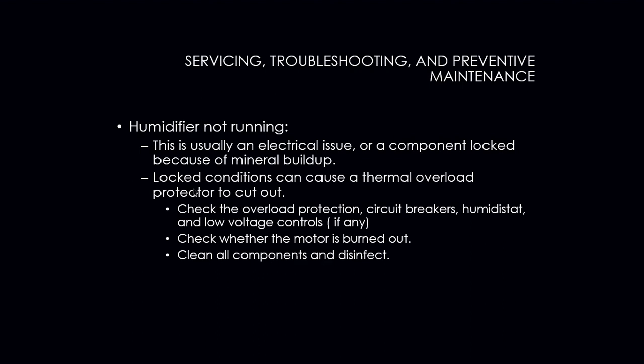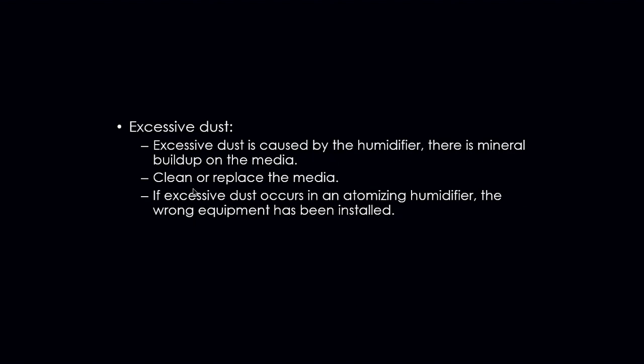Okay, you want to check the overload protection on a humidifier. You want to make sure the circuit breakers, your humidistats, any sort of voltage issues, low voltage controls, all that stuff is on and functioning. You need to check whether or not the motor is burned out on a humidifier. We need to make sure that all of the components are clean and disinfected. Okay, so remember, we are doing maintenance on services. We have to make sure that these things are clean.